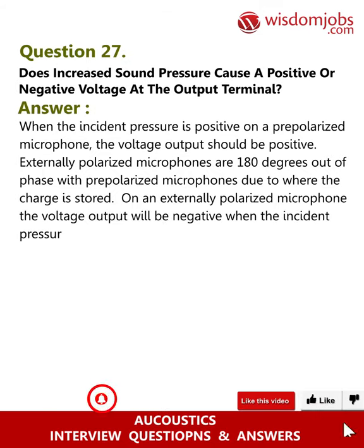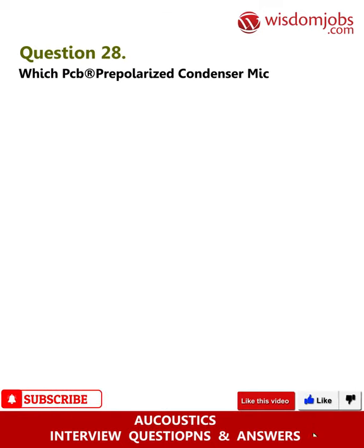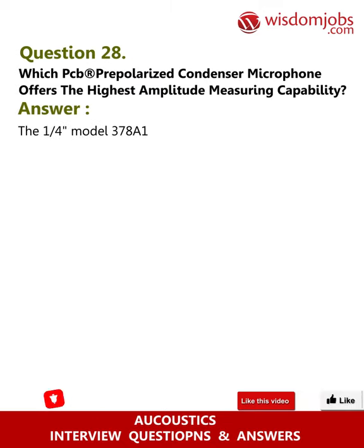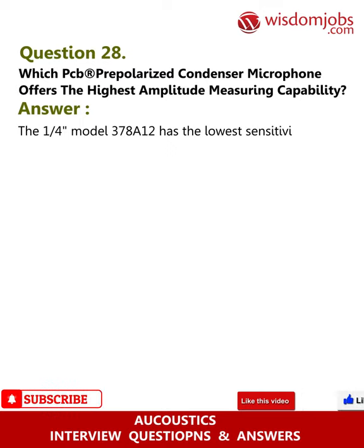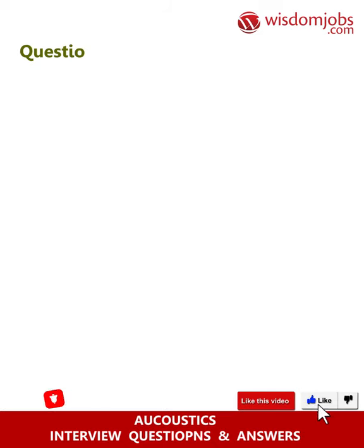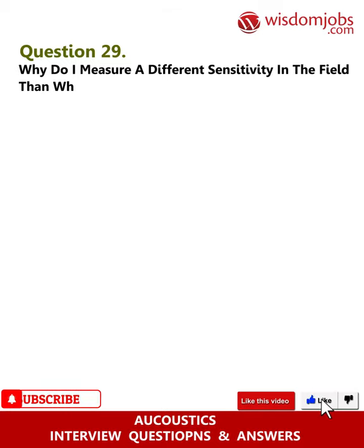Question 28: Which PCB pre-polarized condenser microphone offers the highest amplitude measuring capability? Answer: The one-quarter-inch model 378A12 has the lowest sensitivity at 0.25 millivolts per pascal. This allows it to measure extremely high amplitudes.